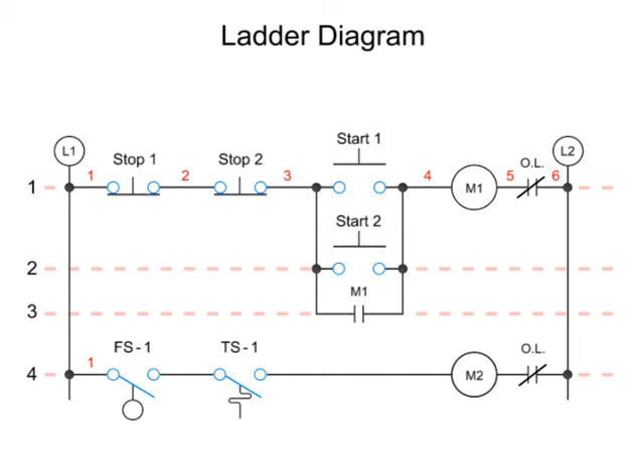The wire between L2 and its nearest contact on rung 4 is also assigned the number determined on the first rung, in this case 6. The remaining wire segments between L1 and L2 are a continuation of the count from rung 1. Thus, you have wires 7, 8, and 9.